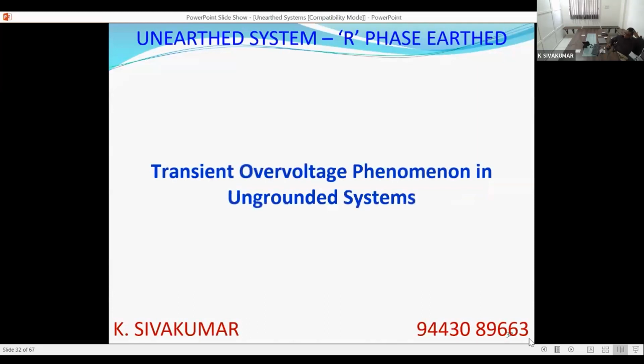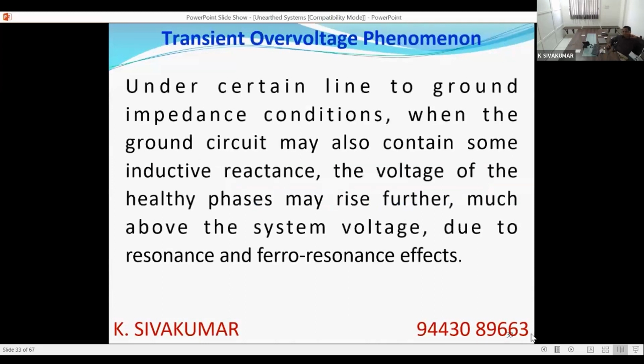The biggest disadvantage is that during an earth fault, transient overvoltage happens in an ungrounded system. Let us analyze what happens. Under certain line to ground impedance conditions, the ground circuit will contain inductive reactance and the voltage of the healthy phases may rise further. It may even go to 5 to 6 times or more. We call this condition resonance and ferroresonance. We will see how it goes.